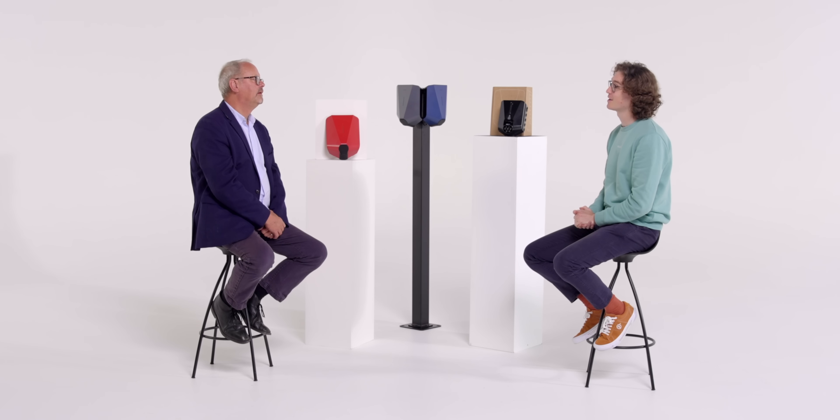So, Charlie, what are the next steps then for Easee? Because clearly you've achieved quite a lot already. Where does it go now? Thank you very much. So what's next for us is we want to bring out the equalizer, as I was mentioning in the commercial sense, but we want to bring it to the domestic space. So now your charger can balance with your home. So if you turn on the oven and you turn on the dishwasher, all at the same time, the charger will say, OK, hang on, I'll slow down a little bit just to keep your house fused safe. And then after that, we also want to look at solar. So we want to enable our drivers out there to charge their cars from their solar panels. And so this is a really cool feature that the market's quite used to. And we'd like to introduce that as soon as possible.